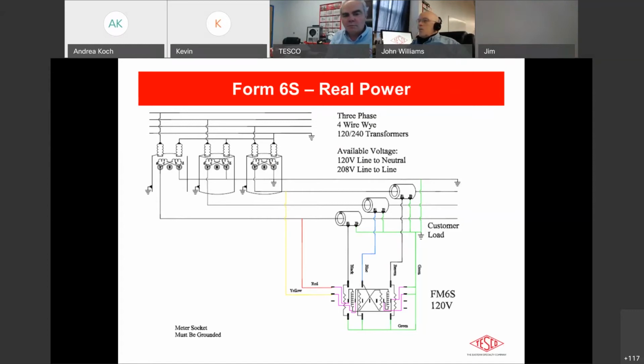Well, this is the one that we started off the presentation by talking a bit about. It's exactly a 2.5 element meter. Blondel says that you can measure n conductors with n minus 1 elements, but this has n minus 0.5 elements, which kind of knocks it out of Blondel's equation. So, these things were in great use for a long, long time, but because of the B, we really need a good voltage reading on the B these days. So they're converting any of this 2.5 element stuff over to 3 as quick as they can up here anyway.